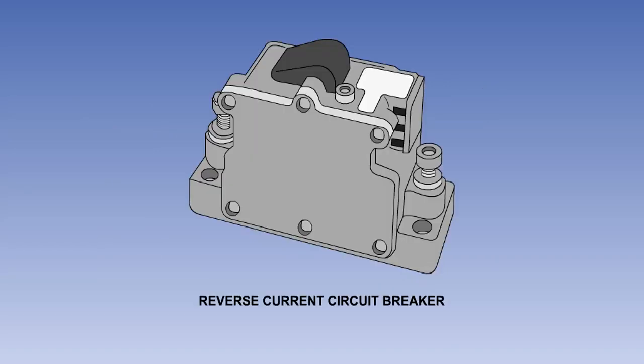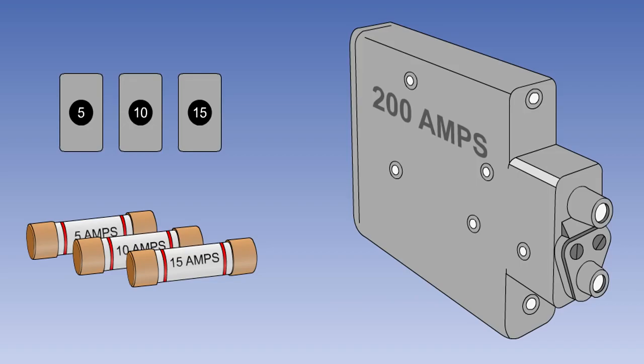Some larger circuit breakers may also include electromagnetic and reverse current tripping devices. As with fuses, circuit breakers are current protection devices and are rated in amperes. Small single-button circuit breakers are rated from 1 to 45 amperes, whereas large circuit breakers can be rated up to 600 amperes.